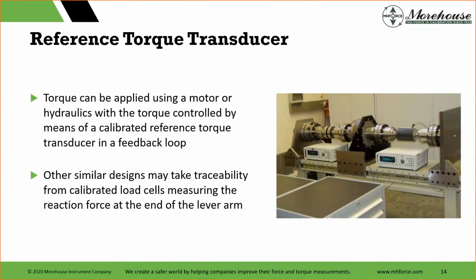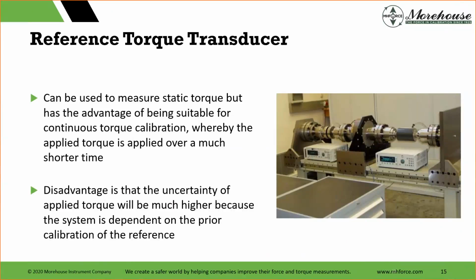Another reference type of torque transducer you can see here is where torque is applied using a motor or hydraulics, with the torque controlled by means of a calibrated reference torque transducer and a feedback loop. Other similar designs may take traceability from calibrated load cells, measuring the reaction force at the end of a lever arm. That's something, we sell a lot of load cells. Some of the customers will have us calibrate load cells in force, and then they'll use their lever arm. They can be used to measure static torque, but have an advantage of being suitable for continuous torque calibration, whereby the torque is applied over a much shorter time. And a disadvantage is that the uncertainty of applied torque will be much higher because the system is dependent on the prior calibration of the reference.